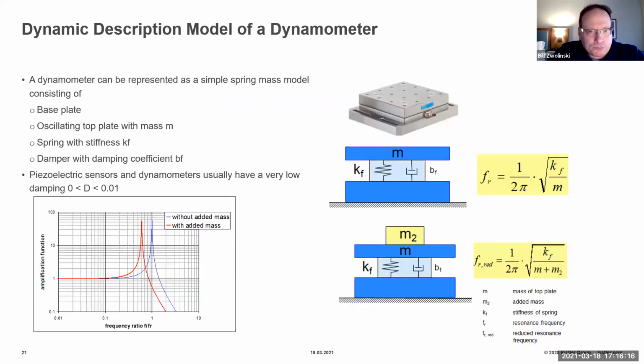Also, with regard to dynamometers that I mentioned, dynamometers are basically force plates with multiple 3-component force sensors in them. They basically act as a spring mass system. So with any spring mass system, if you add mass, you're going to reduce the natural frequency. And this is a physical rule. It's the same for strain gauge as piezoelectric. So keep that in mind as you're building a capability to measure certain frequencies. A lot of times, if you need high frequency measurement, piezoelectric is absolutely the first choice. And a lot of times, added mass doesn't have as big an effect with piezoelectrics as it does with other technologies. So it's something to think about when you're taking your measurement.